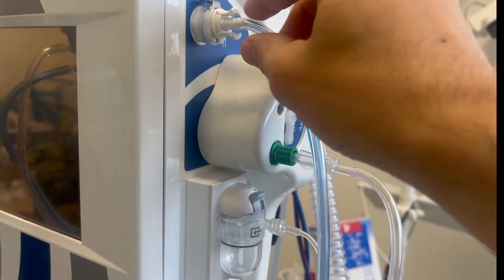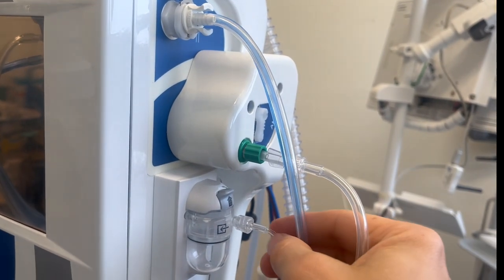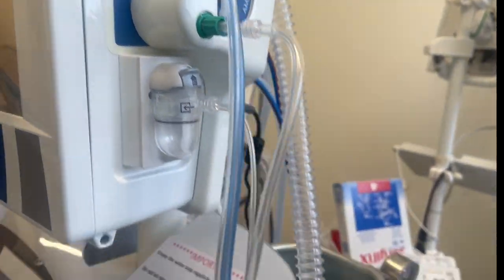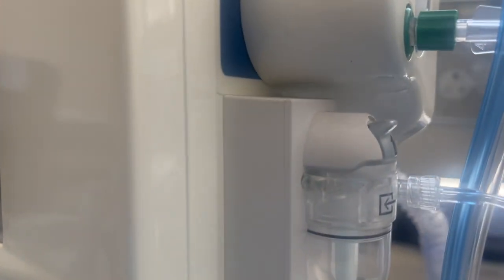Ensure all your disposable lines are connected securely, as this can be a common reason for the system delivery test to fail. Find the green adapter at the end of the circuit and follow the line back to the water trap to ensure that the circuit has been connected in the correct orientation.